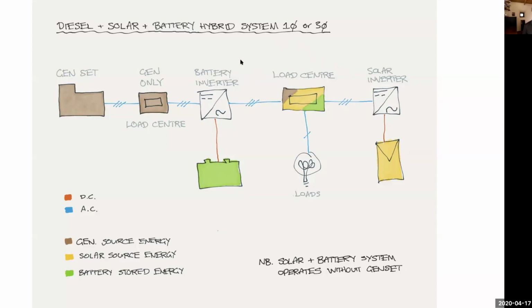So what I could do is put in a very small array, maybe just a couple of panels - a small array that through a charge controller directly connects onto the battery and tops it up. That means if a black start condition were to occur, particularly at nighttime, when the sun comes up in the morning, that little DC coupled system kicks in. Now I haven't drawn a charge controller in there, but I should point out you need some way of protecting that system from overcharging the battery - so that little thing there is a charge controller.